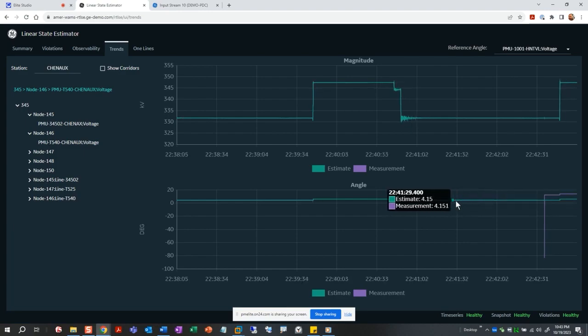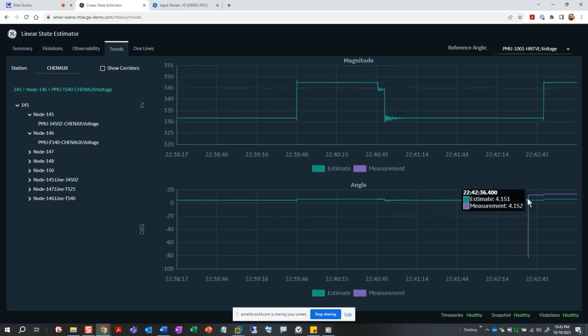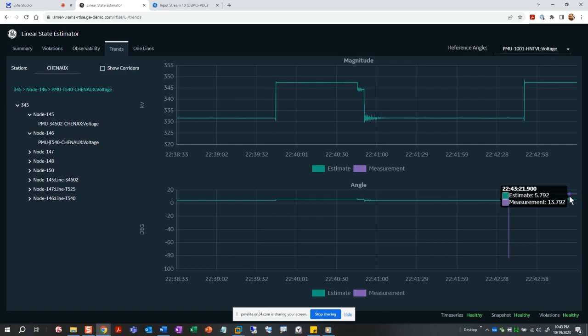So when they were in alignment with each other, there was no offset. They were solving directly on top of each other. So our estimates and our measurements are directly in line. And when I put in that 8-degree offset, which happened here at this moment in time, you can see that the measurement is still coming in with an 8-degree differential, but the estimate is correcting for that and putting in the correct value. So it's solving around the incorrect poor data that's coming from the PMU out in the field.